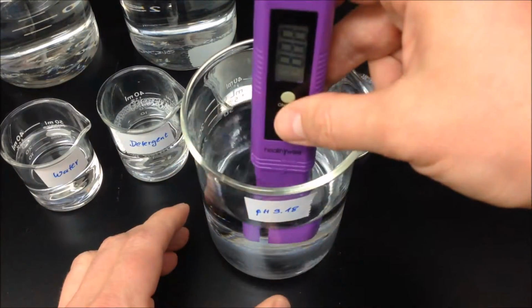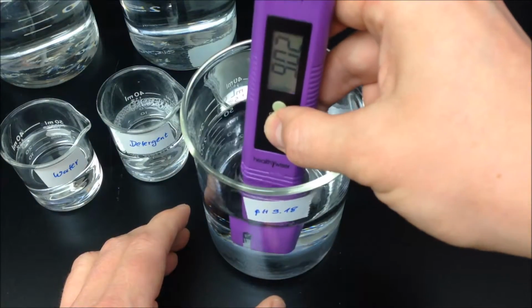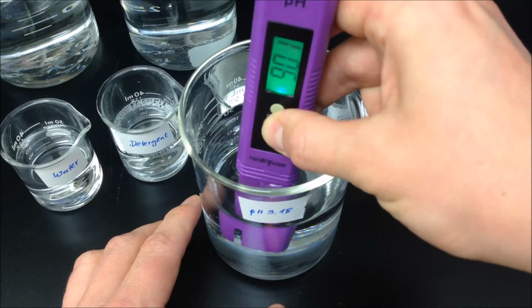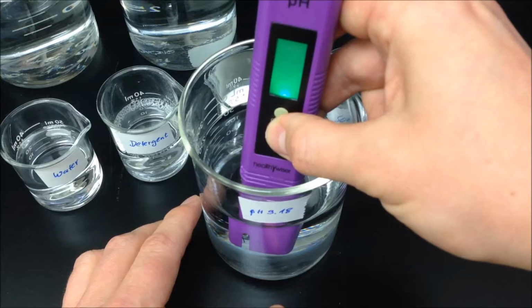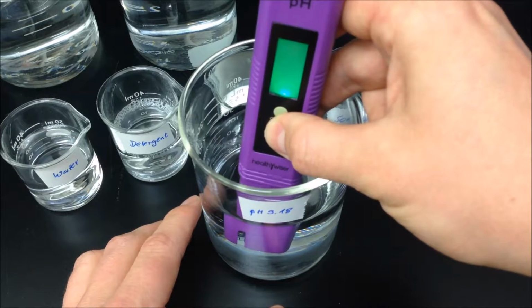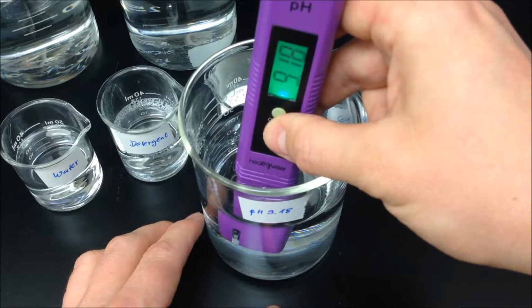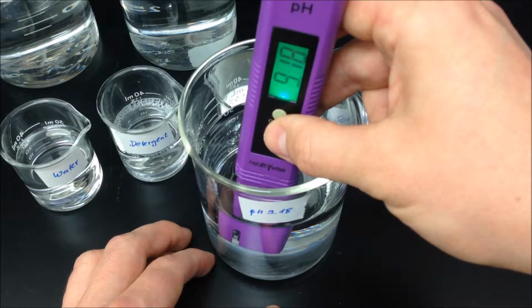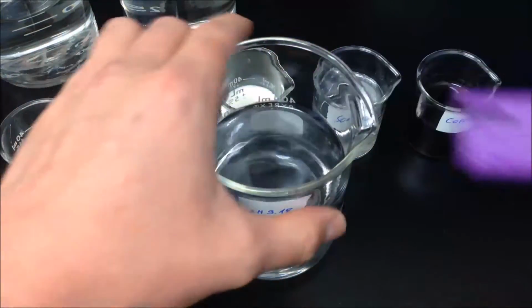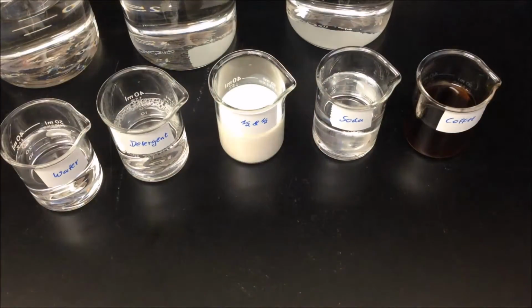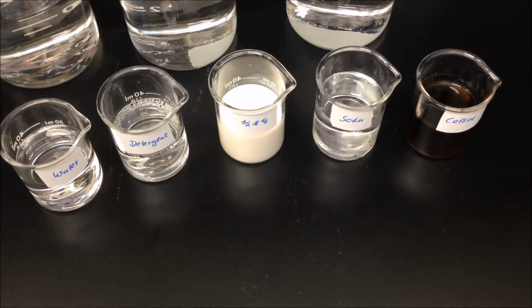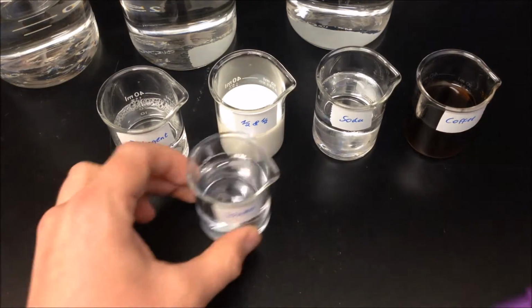And then we take the higher calibration solution, and again I'll go in there, I'll push 3 seconds calibrate button and release, and then I push 2 more times, and now it calibrates for 9.18, and it stopped flashing. Alright, so now it should be calibrated between 6.86 pH and pH 9.18. Alright, so let's check that. The water.